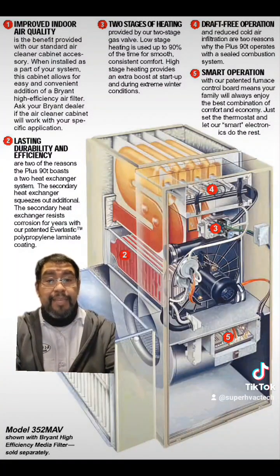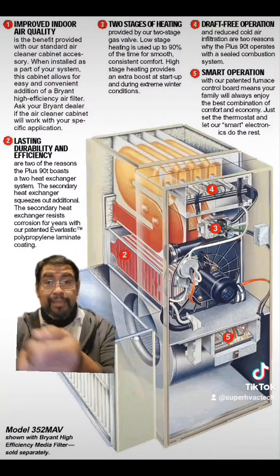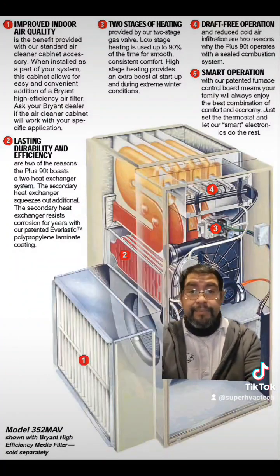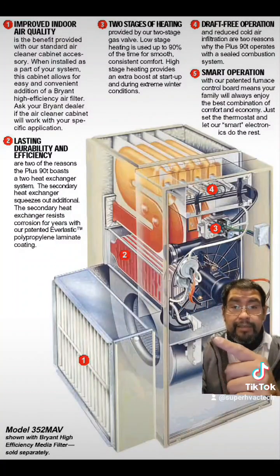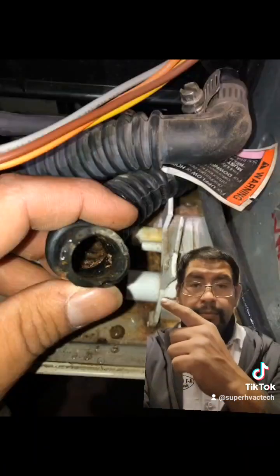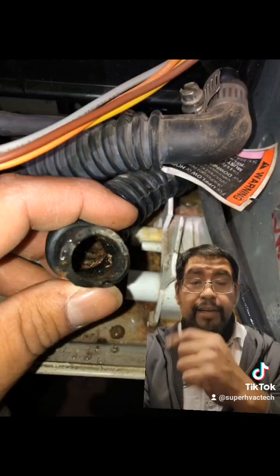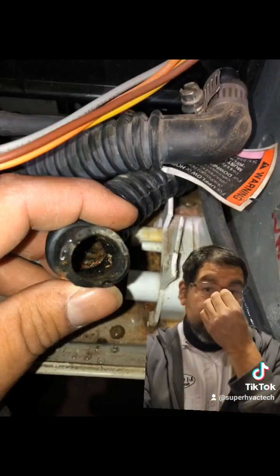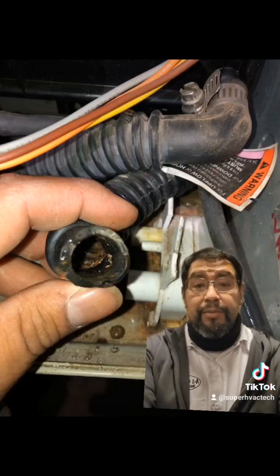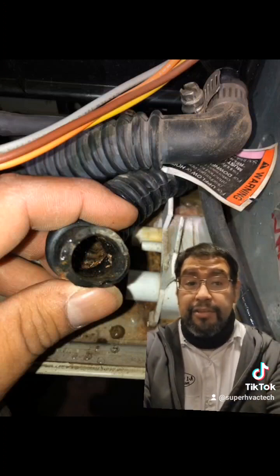Basically, they put a liner on that heat exchanger. Well, that liner will actually start to deteriorate at a relatively low temperature. So if you ever take the drain right there, and if it looks like it's starting to look like that, if you look in there, there's going to be plastic shavings. That's from the heat exchanger. That's your telltale sign that the heat exchanger is on its way out.